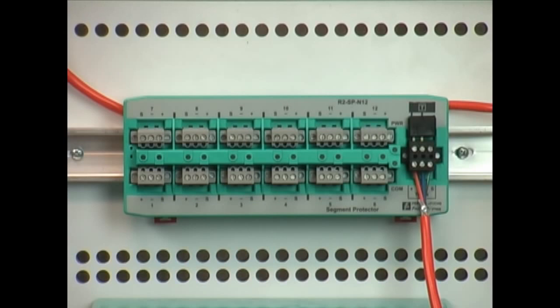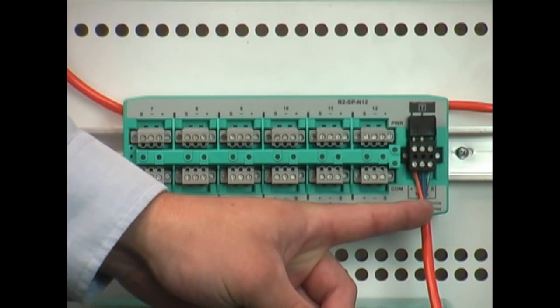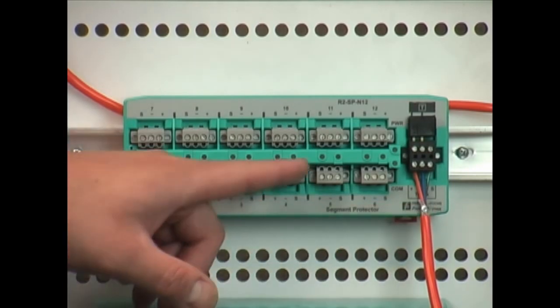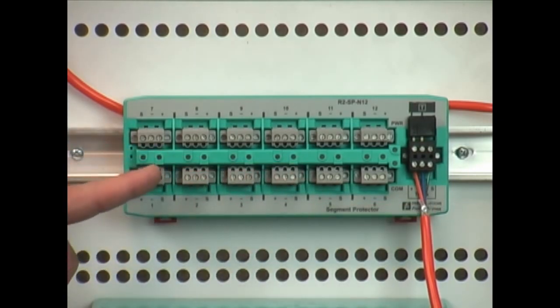The next component for a Foundation Fieldbus segment is going to be some sort of field distribution and for Pepperl and Fuchs we call that a segment protector. This is what takes a trunk in connection from your power supplies and converts that into different spur connections for your individual field devices.